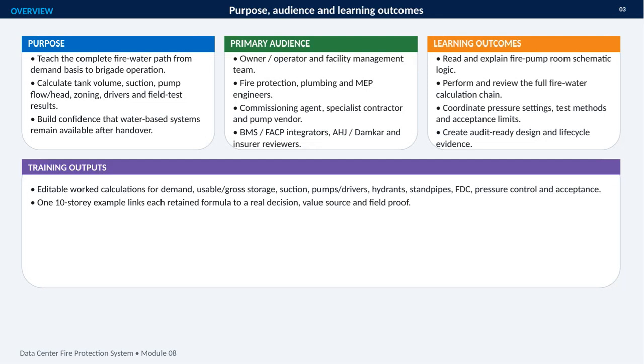Its purpose is to teach the complete fire-water path, from establishing the demand basis through brigade operation, and to show how each design decision can be calculated, checked, and demonstrated in the field. We will cover tank volume, suction conditions, pump flow and head, system zoning, drivers, and field test results.